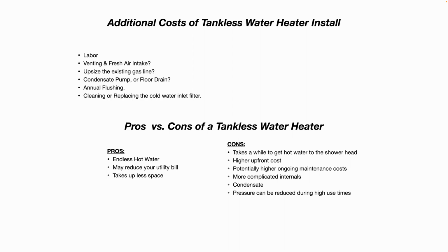And then if you have a condensing model, they do make non-condensing tankless water heaters, but we're talking about the high efficiency condensing models. That condensate has to go to a drain. If you don't have a drain, then you need to get a condensate drain pump to pump that condensate to a drain. And then the other weakness or con about tankless water heaters is your water pressure can be reduced during high use times. So say you go in and take your shower and somebody starts a load of laundry, or somebody starts the dishwasher, or they're washing their hands or shaving or brushing their teeth in another bathroom, you may find a reduction in your water pressure at your shower.